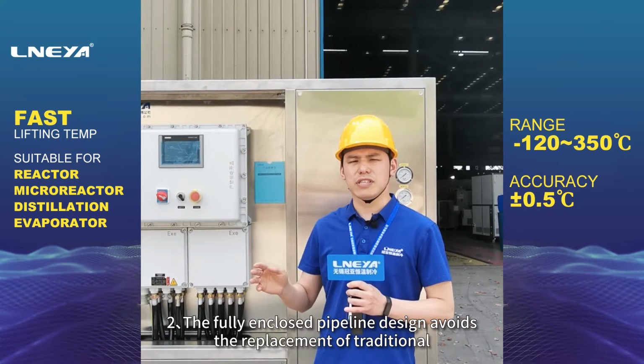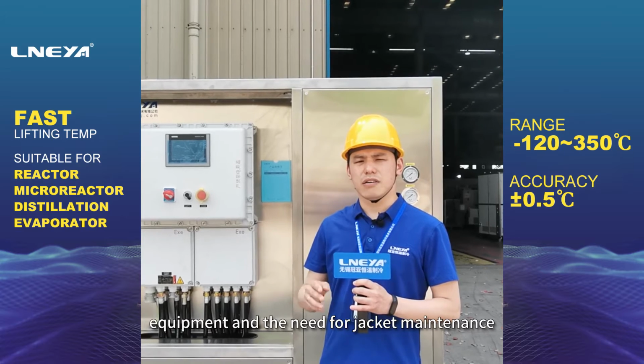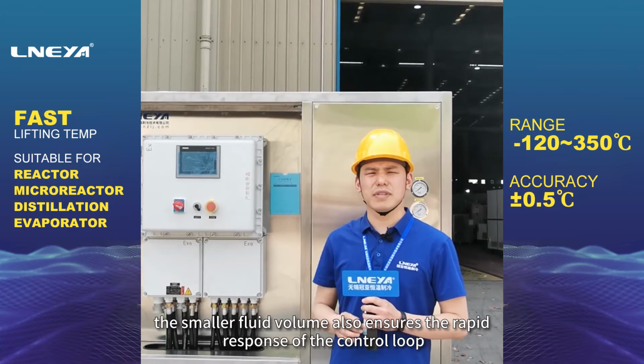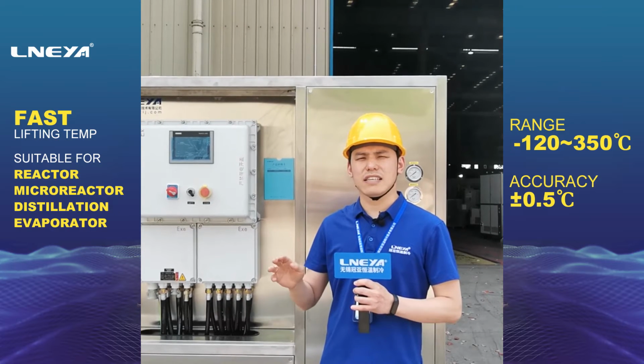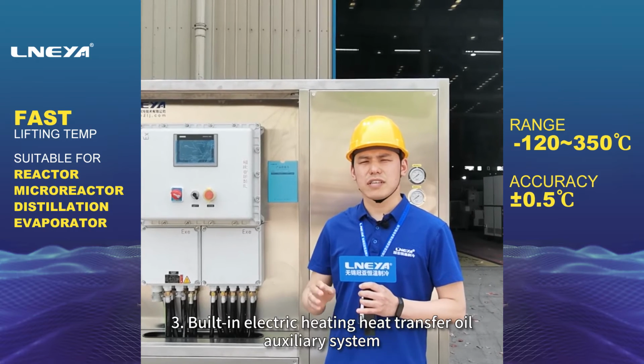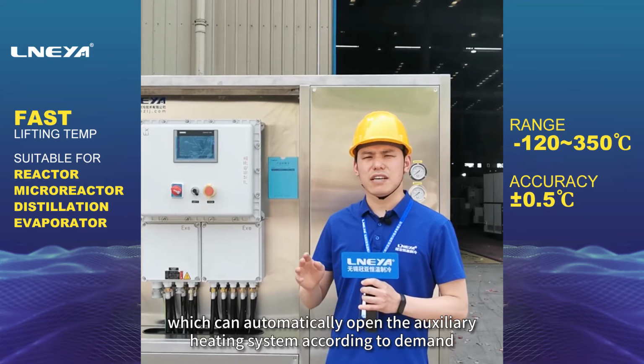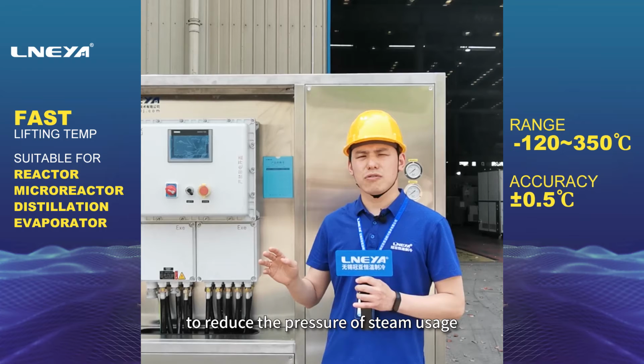Second, the fully enclosed pipeline design avoids the replacement of traditional equipment and the need for jacket maintenance. The smaller fluid volume also ensures the rapid response of the control loop and the thermal response delay is small. Third, built-in electric heating heat transfer oil auxiliary system, which can automatically open the auxiliary heating system according to demand to reduce the pressure of steam usage.